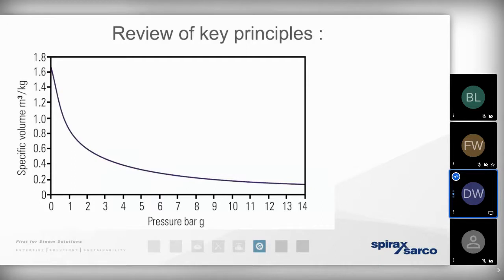And we also know that there's another relationship to take into account. There's the pressure to volume relationship. So if we're distributing a kilogram of steam at a high pressure, 10 bar gauge, for example, it's going to occupy a volume of approximately 0.177 cubic meters. But if we reduce the pressure of that steam at the process in order to satisfy the temperature requirements on the secondary side, then the volume is going to expand considerably. And this reminds us why we've got a benefit of keeping the steam at a high pressure, but it also reminds us why we need to size the distribution pipework accordingly.